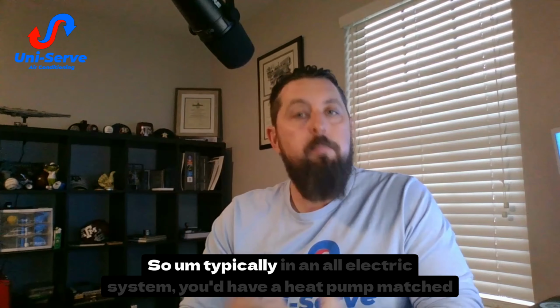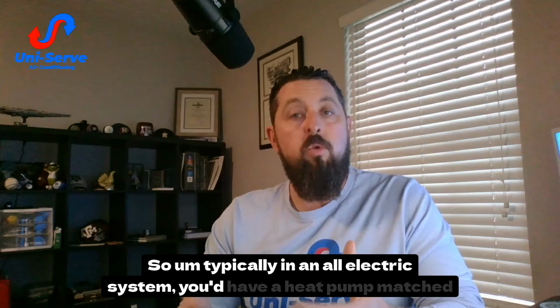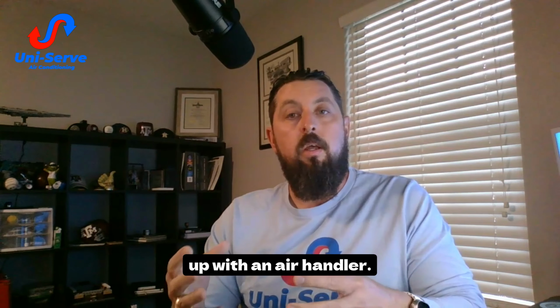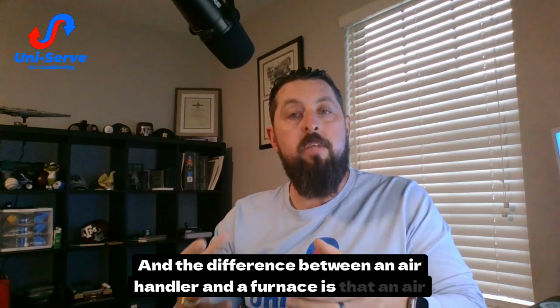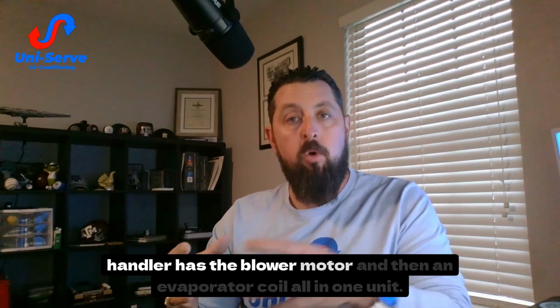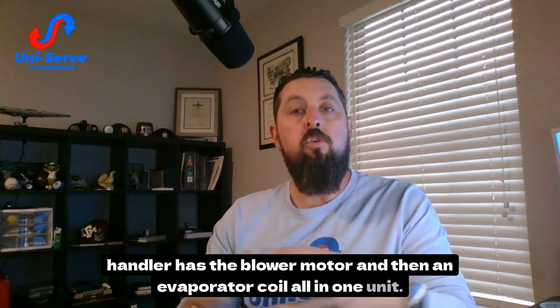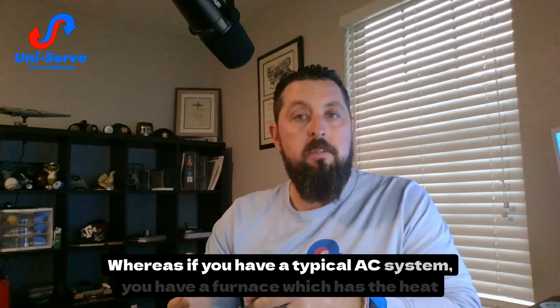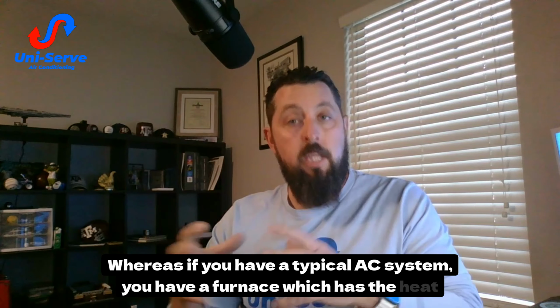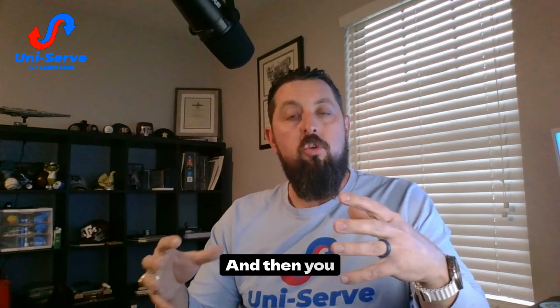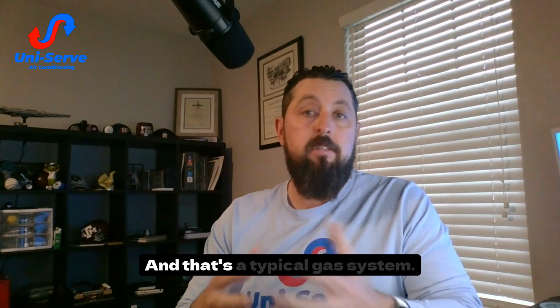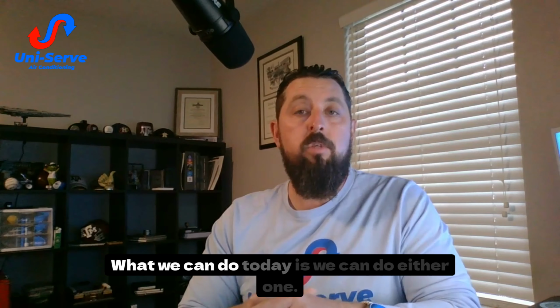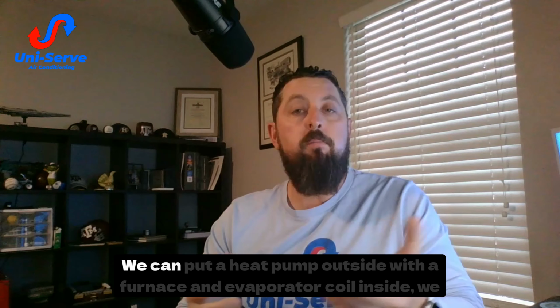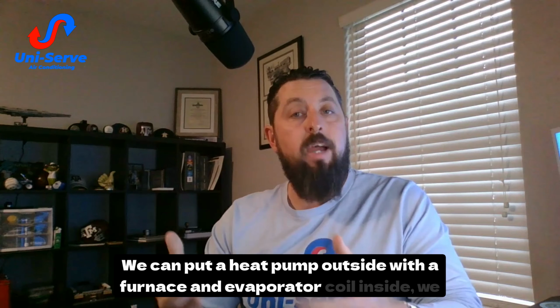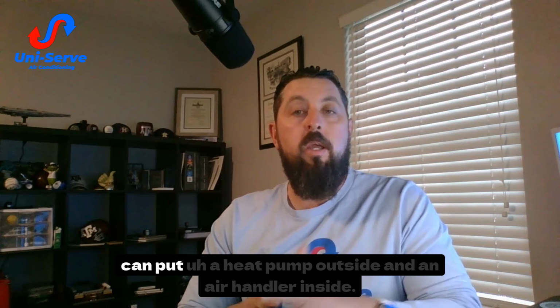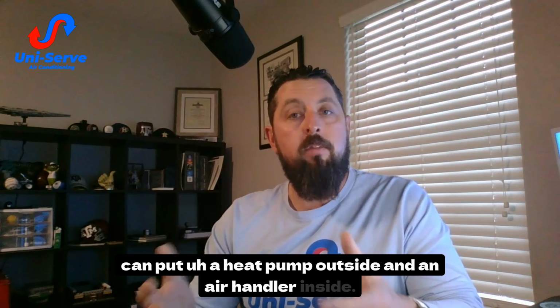So typically in an all-electric system, you'd have a heat pump matched up with an air handler. And the difference between an air handler and a furnace is that an air handler has the blower motor and then an evaporator coil all in one unit. Whereas if you have a typical AC system, you have a furnace which has the heat exchanger and the blower motor, and then you connect that up to an evaporator coil. And that's a typical gas system. What we can do today is we can do either one. We can put a heat pump outside with a furnace and evaporator coil inside, or we can put a heat pump outside and an air handler inside.